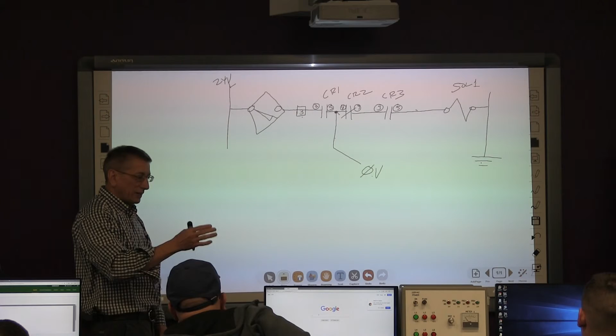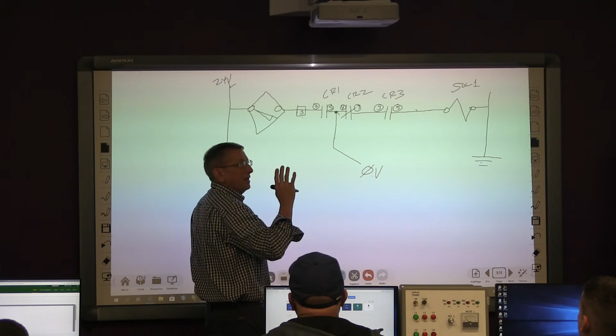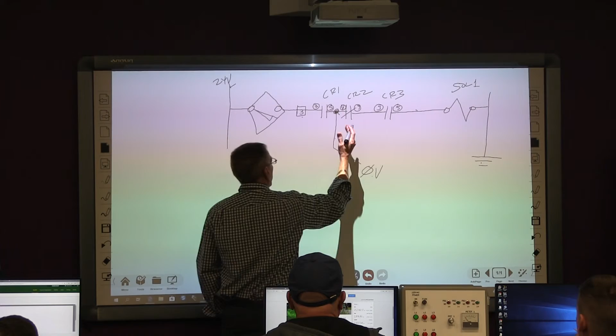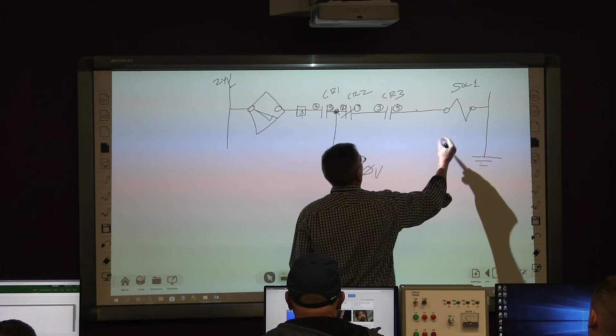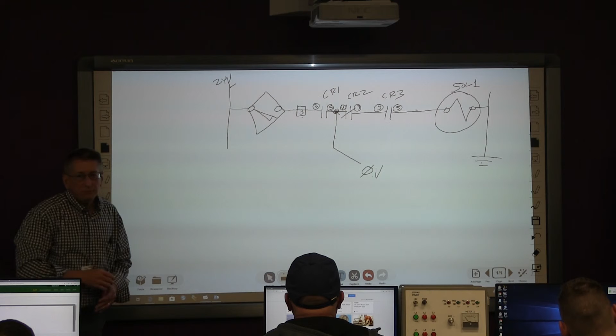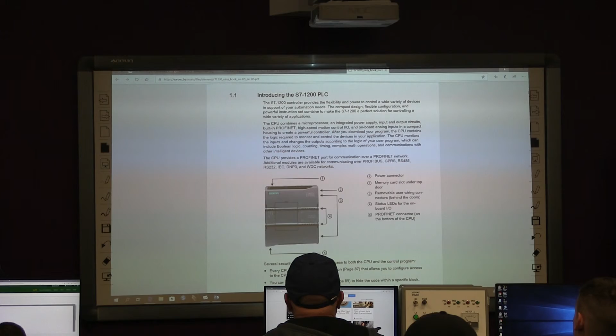Does it make sense? Yeah, you avoid wasting a lot of time by doing careful observation and being very thorough. But the point is, in the PLC troubleshooting world versus the electrical hardwired world - in hardwired, we start somewhere in the center and measure back. In PLC troubleshooting, we start at the output, because if you start in the middle somewhere with all that ladder logic, you're going to be lost. So we're going to go through some of those right now and practice a little bit.